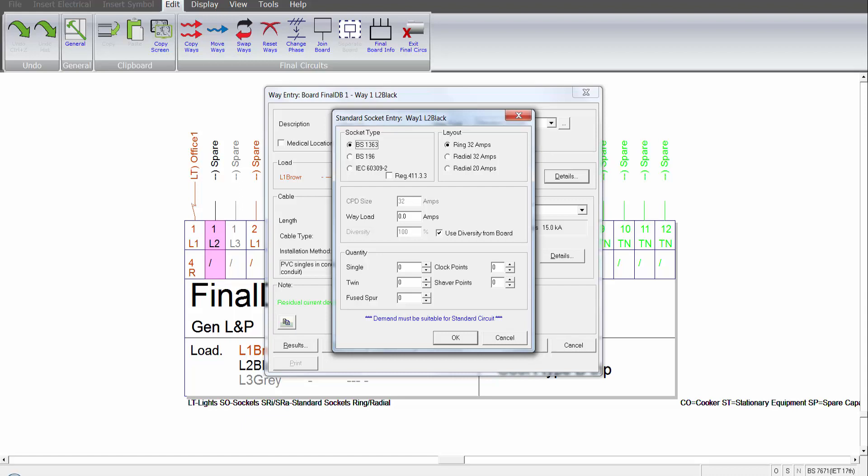As far as the load on the circuit is concerned, I could apply the full 32 amps at 100% or I could apply the envisaged way load at 100% or I could put 32 amps in and apply their diversity. So whether the loading can be expressed as a full load where diversity is applied or I can put the entire load in with no diversity and put the anticipated circuit loading in.